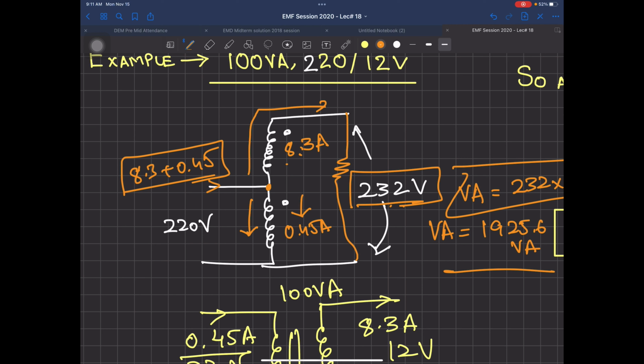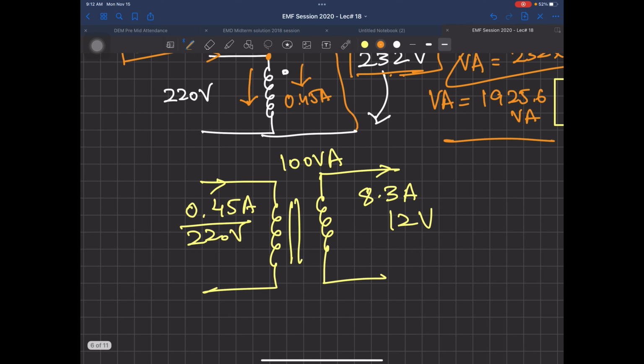If you remember the motor I told you about, I showed you, I guess it's still in my bag - I told you that motor was rated for 110 volt and my mother plugged it in for 220 volt. Every winding has an insulation rating. When you designed this transformer, the secondary winding was only rated for 12 volts.